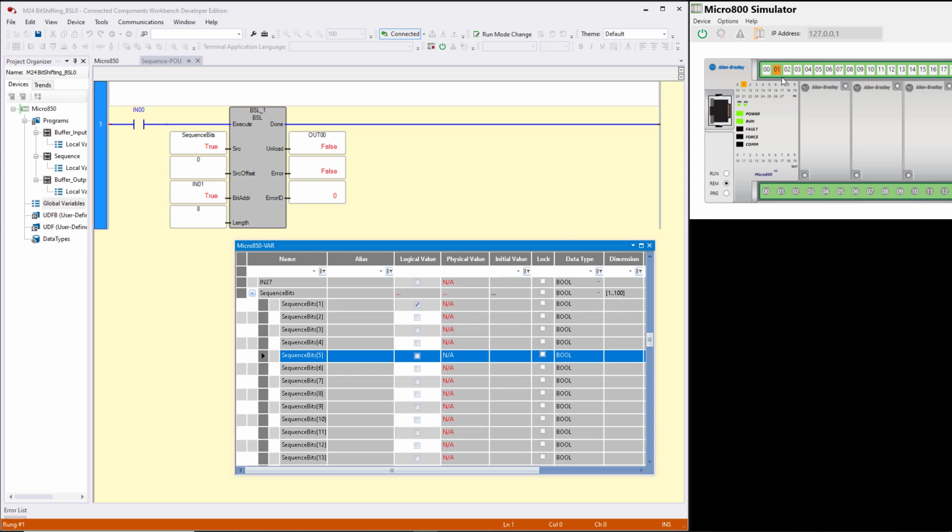Okay, I'm going to turn off input 1, and then I'm going to turn on 0. So watch the value of bit 1 and bit 2. I'm going to toggle 0 on and off, and you see it moved. It shifted. Now, it's shifting down on the page, but it's shifting from the least significant bit towards the most significant bits. That was one shift from bit 1 to bit 2, and it pushed a new 0 into bit 1. Of course you can't see that because you can't see it change from 0 to 0. There's nothing to see.